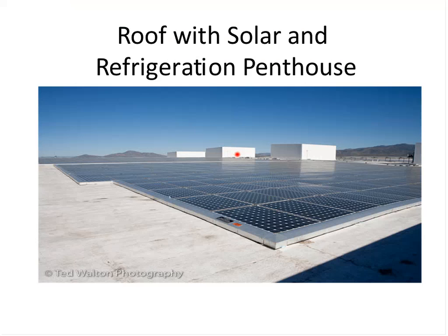Here's looking at the roof. These penthouses right here are where the evaporators are. There's 4 of them. So then accessible through a standard door here. So to provide maintenance on the evaporators, it's access through the roof. This is in lieu of hanging the equipment inside or on the walls. And of course you can see the photovoltaic panels. That's about 1.1 megawatt, and it supplies roughly 70% of the power for the site just from those panels. So interesting, can be done, and this was all achieved in a cost-effective fashion.